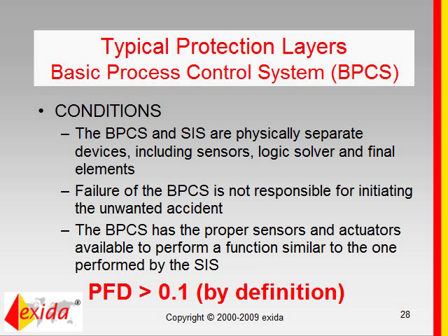If you use a safety certified PLC to perform your control, then it's a different story. You could go with a probability of failure that is less than 0.1, but again, that's when you have a safety PLC that is developed per 61508.